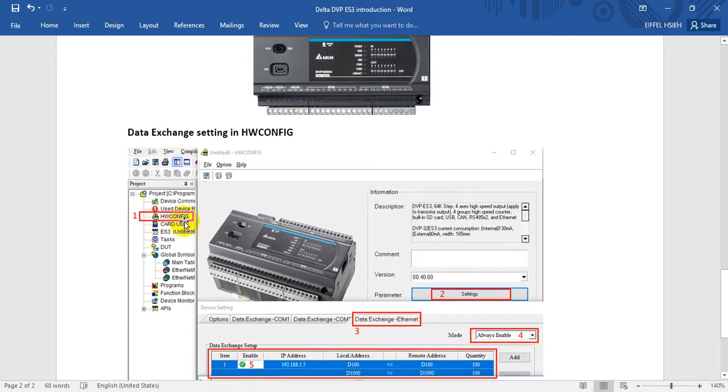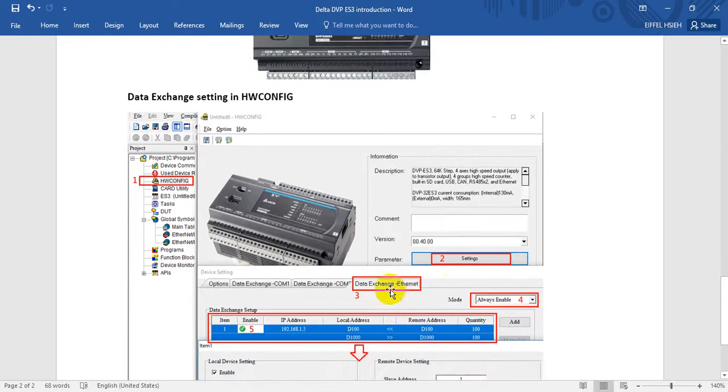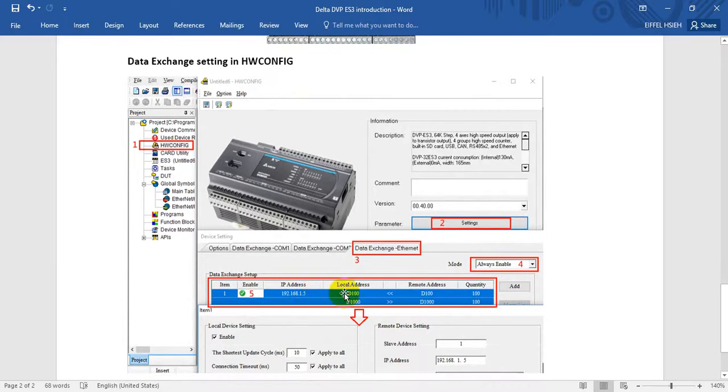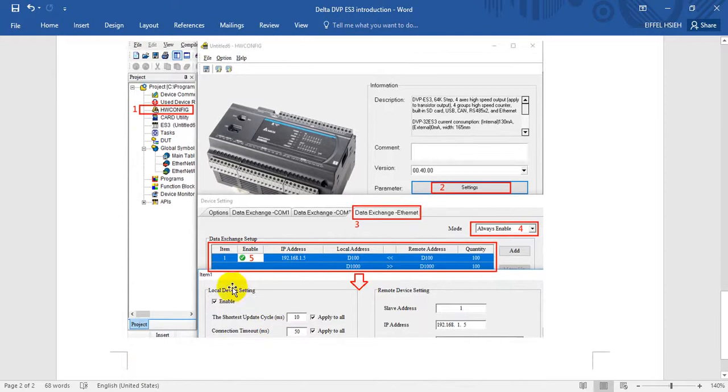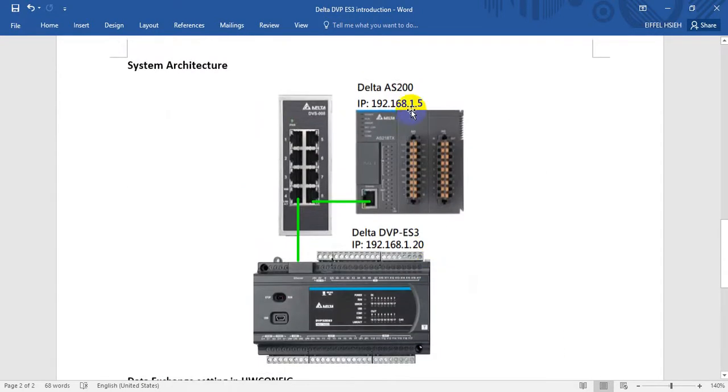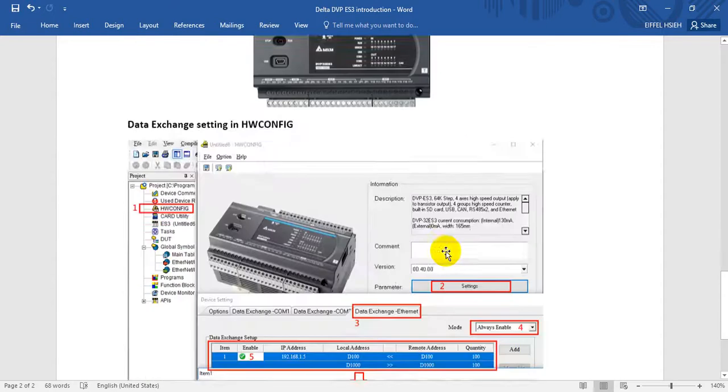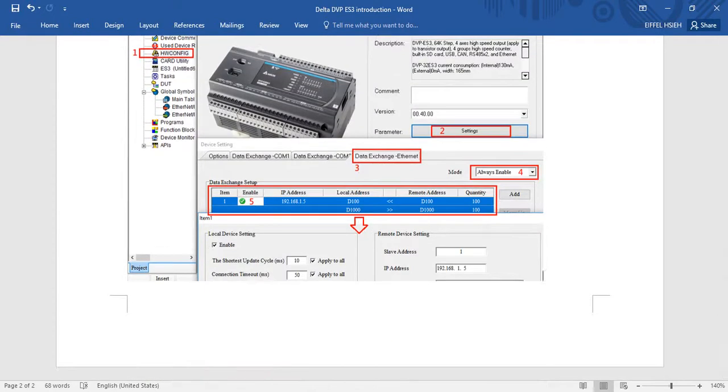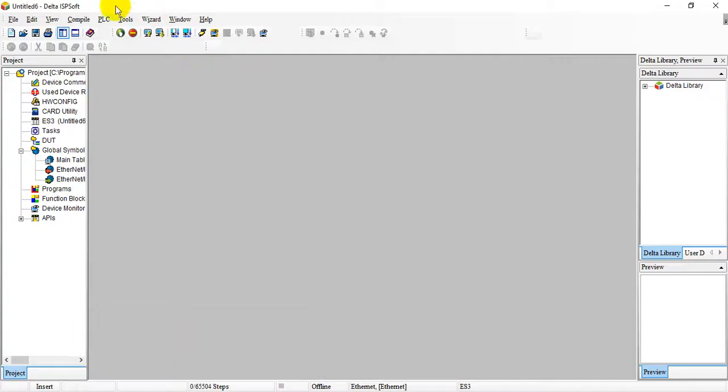First step, we double click the hardware config. This will pop up, and we can click the setting and go to data exchange over Ethernet and select enable. Then we can do some settings over here and remember to assign the address. The address is 1.5 because we want to get the data from AS200. Now let's go back to software again.